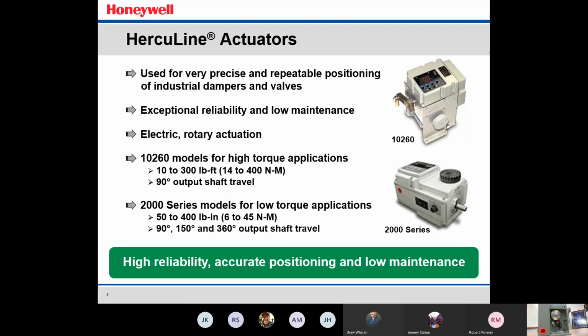These also offer a slide wire feedback control. In the old days, it was called PAT, or position adjusting type, and that would be considered a slide wire feedback control that utilizes a non-contact feedback signal into the control loop from the actuator, and then from the control loop, an increase and decrease digital output to the actuator to position it. We'll get into the electronics a little bit later in the slides, but just to know that you can do either 4 to 20, on-off, or position proportional control with either one of these actuators.